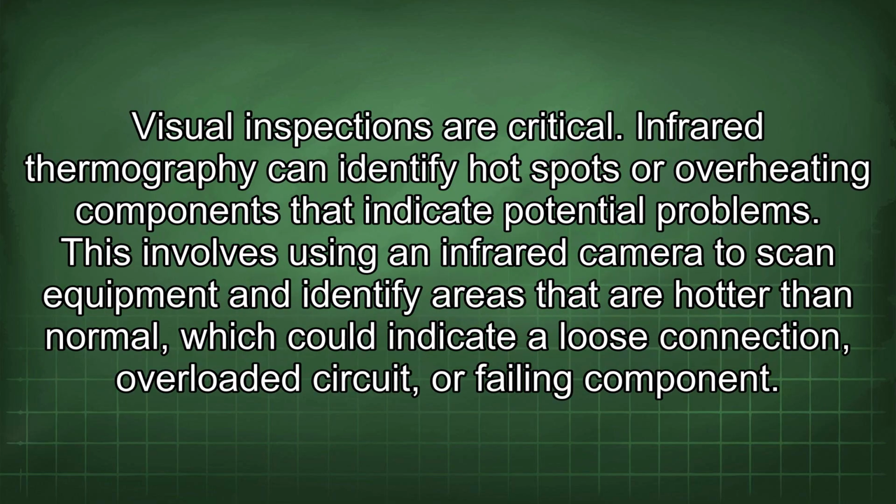Visual inspections are critical. Infrared thermography can identify hot spots or overheating components that indicate potential problems. This involves using an infrared camera to scan equipment and identify areas that are hotter than normal, which could indicate a loose connection, overloaded circuit, or failing component.